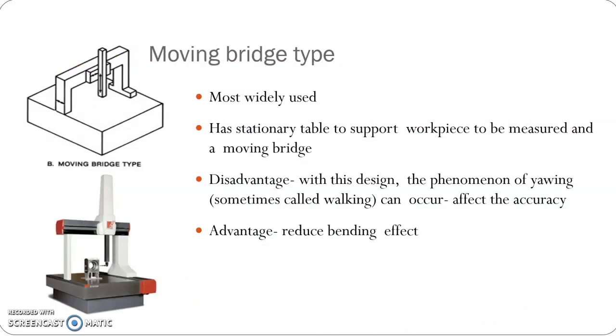In moving bridge type, the vertical probe is fixed on a moving bridge. The bridge moves on the guideway provided on the table, and the movement of the bridge is the X axis. The vertical movement is the Z axis, that is vertical movement of the probe head. The probe also slides on the face of the beam, that is the bridge, and that is the Y axis. This design has a reduced bending effect compared to cantilever type, but the problem is the yawing of these two legs of the bridge.